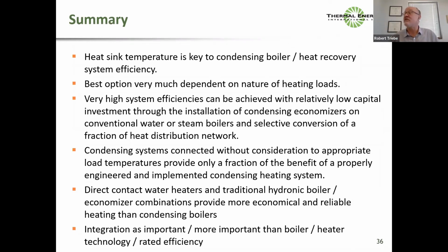Best option is absolutely dependent on the nature of the heating load and the relative proportion. Do I have more user than source? Do I have more source than user? Nine out of ten times you've got more source than user. Very rarely are you able to use more waste heat than you have. Very high system efficiencies can be achieved.